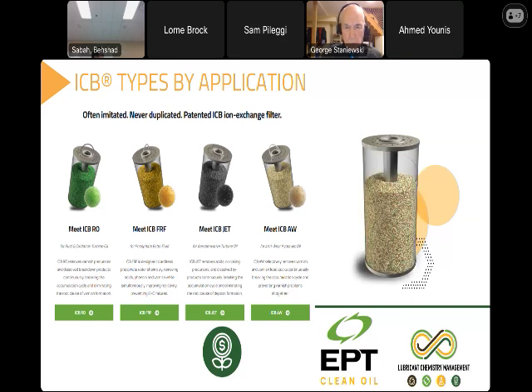These have no additives, very few. RO oils have about 1% additive. Jet lubricants, similar. And then when we get into AW, we're pushing 3 to 5% additive. So we're much more careful about what we can take out when dealing with additized lubricants. Fortunately, the tuning and selectivity of ion exchange resins can be programmed to get around that in most cases. On the heavier additized products, we do testing before and after to make sure there's no impairment in the additive before we position the product in service.